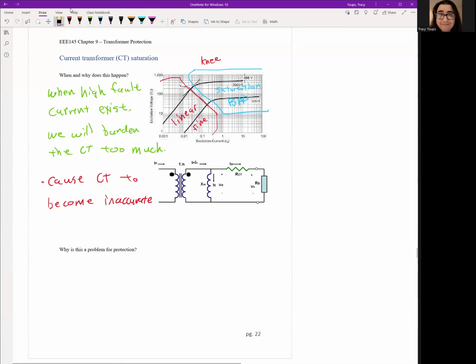Okay. Let me put that on the side. Okay, so in the middle, this is a knee curve. You'll hear it one day. Basically, operate below the knee curve, you're fine. Operate above the knee curve, you're in saturation, you're going to have some issues. Okay. So why is this a problem for protection? We always have to ask that.